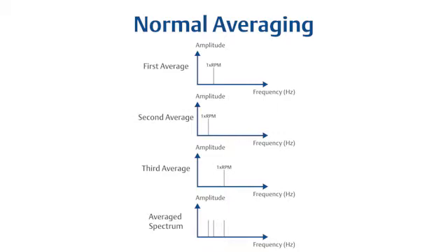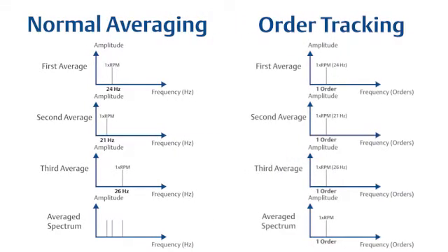Notice in the first average, the imbalance value was at 24 Hz. In the second, the value was down slightly to 21 Hz, but the third average was back up to 26 Hz. So the average spectrum will show you three peaks, but the data is misleading due to the variable speed. But if you can add speed data using a TAC sensor, you can perform order tracking.